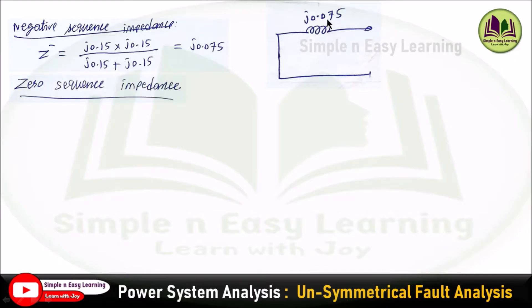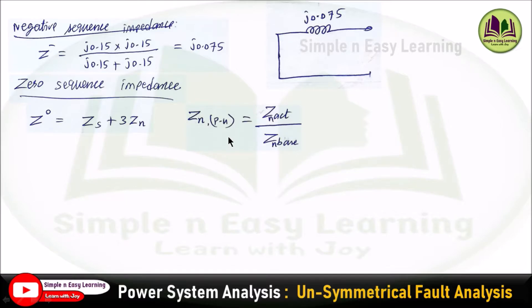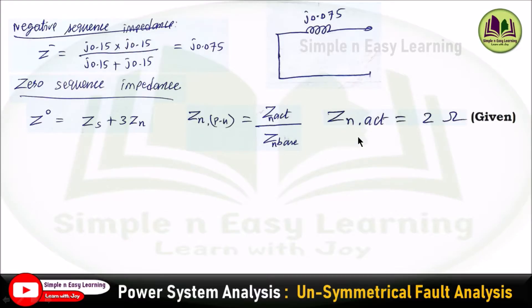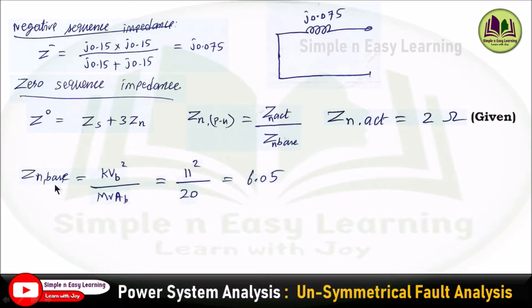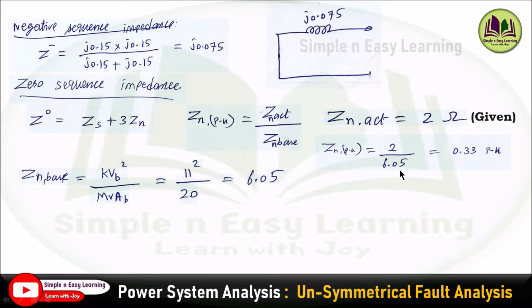For zero sequence impedance, Z0 = Zs + 3×Zn, where Zn is the neutral impedance. Since the neutral impedance is given in ohms, we need the per unit value: Zn(pu) = Zn(actual) / Zn(base). Zn(actual) = 2 ohm, and Zn(base) = KVB² / MVAB = 11² / 20 = 6.05 ohm. Therefore, Zn(pu) = 2 / 6.05 = 0.33 per unit.